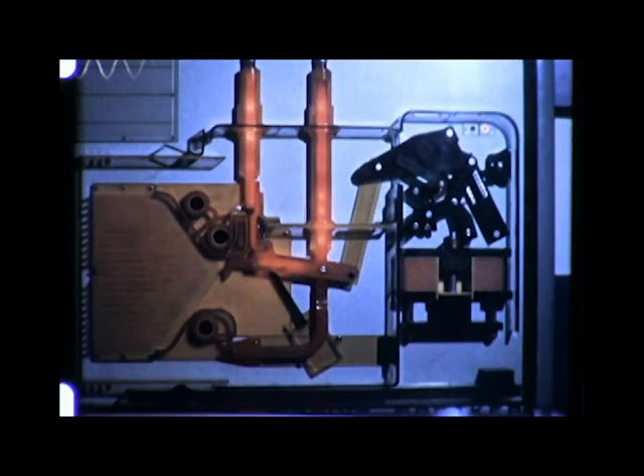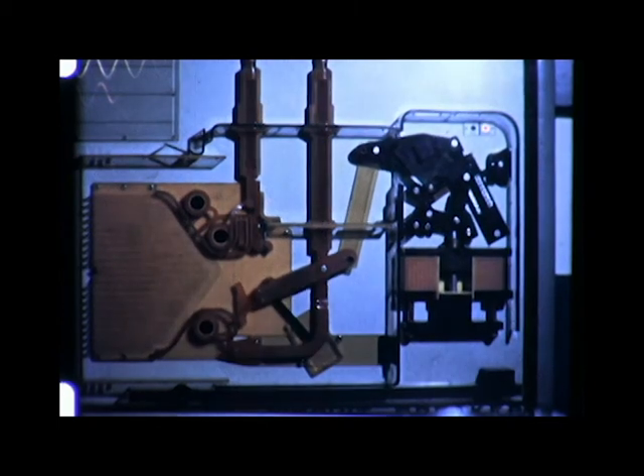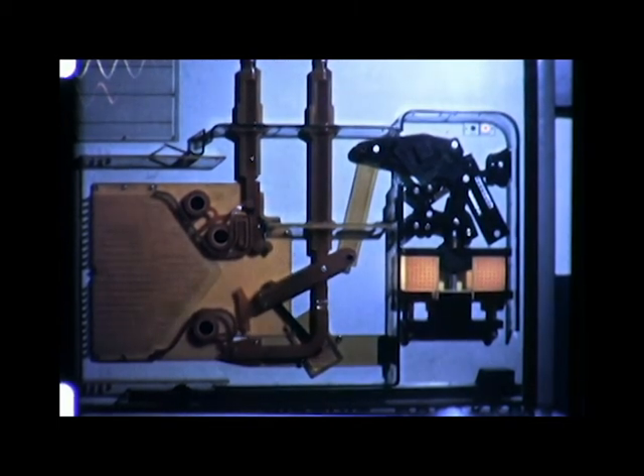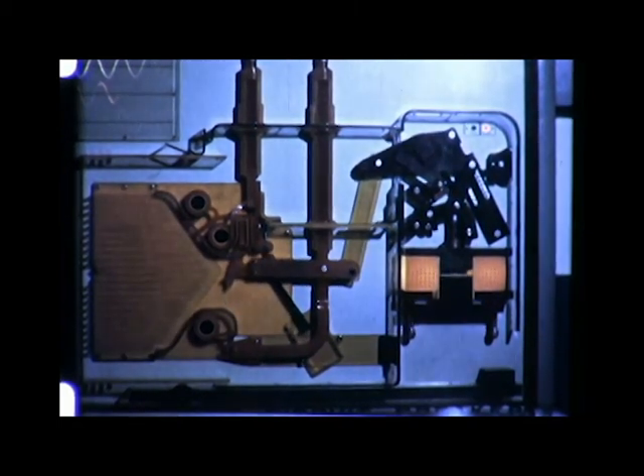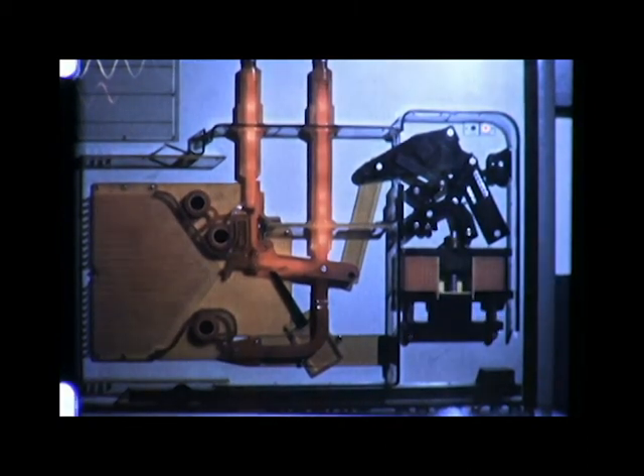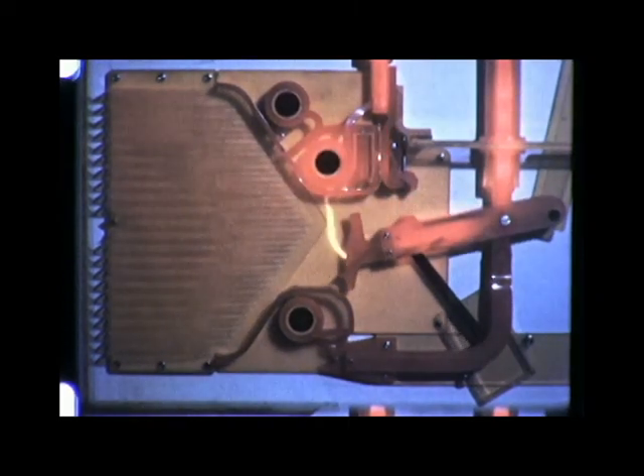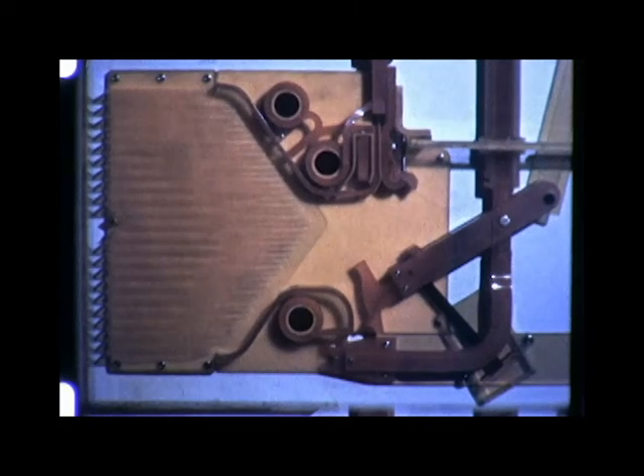A Magne-Blast breaker interrupts a circuit by magnetically forcing the arc into interleaving insulated barriers, known as arc chutes. Barriers stretch the arc and restrict its cross-section. Heat is absorbed by the chute, so that electrical resistance is considerably increased. The arc path becomes so long, and gases produced by the arc so cooled, that the arc cannot reestablish itself, and the circuit is open.